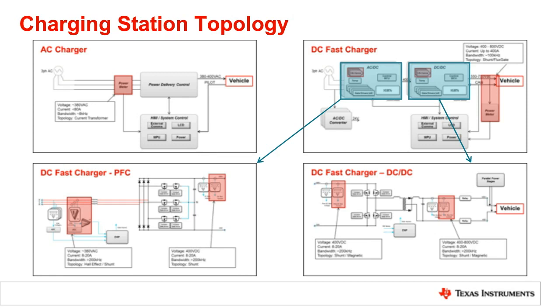But also on the output, the DC bus of the Vienna stage will require some kind of current sensing. The input on these is typically 400 volts AC with a current in the 20 amp range, and the voltage on the output is usually 400 volts DC with the same kind of current ratings. So these kind of loops require a fairly high bandwidth sensing stage, and we'll get into more of those specifications later and why they matter.